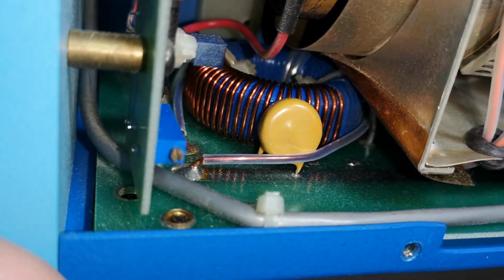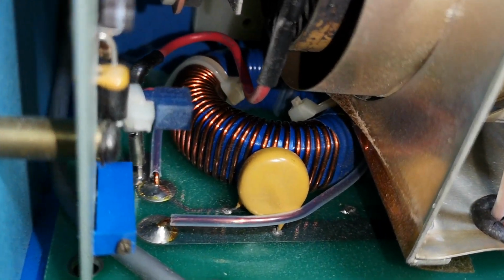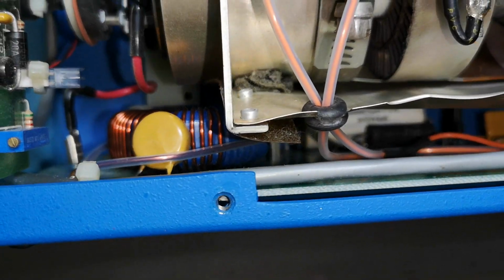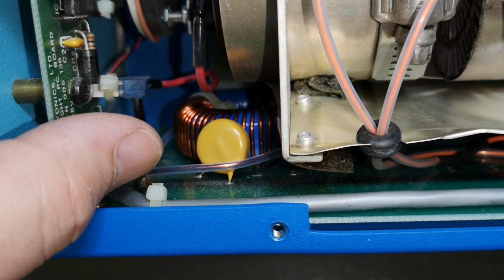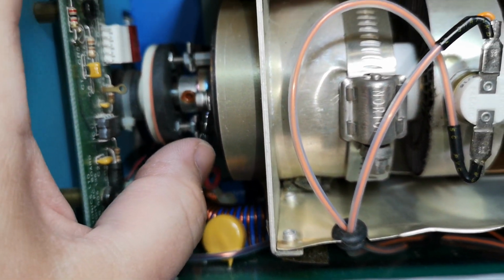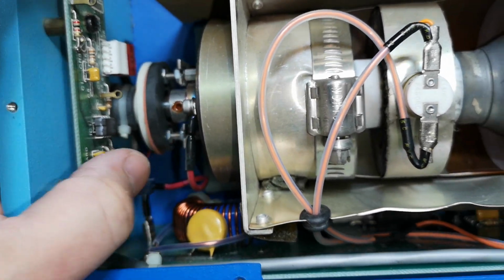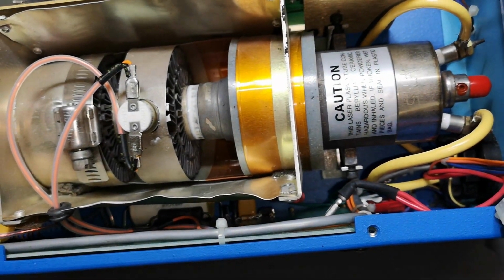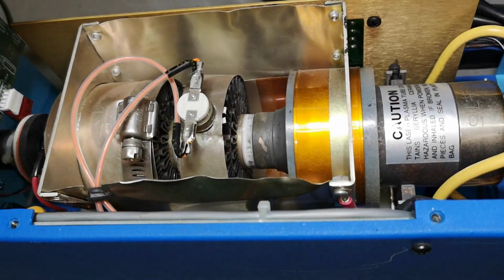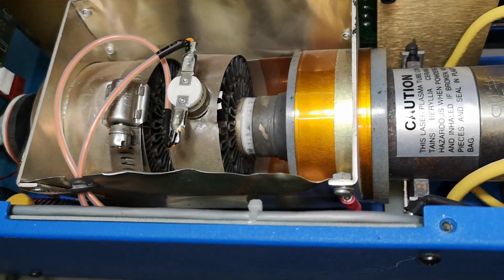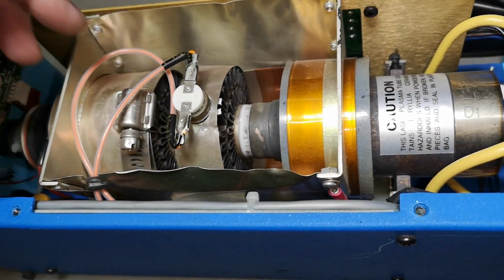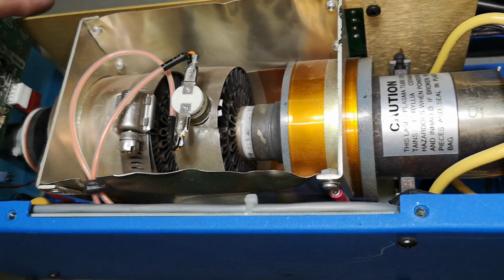We see some other windings - you can probably see them down there. So that generates a high start pulse added on top of the anode supply, and that will make the beam start, right? Then you will have a low voltage, high current.